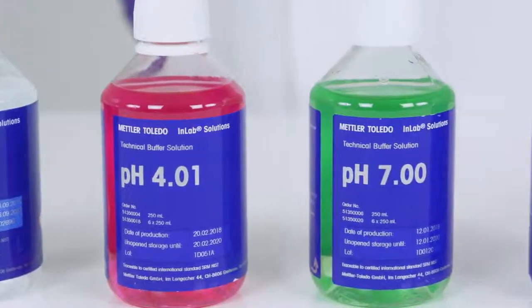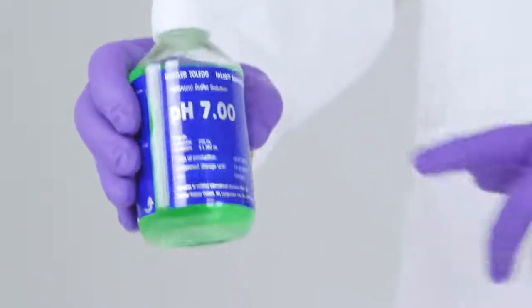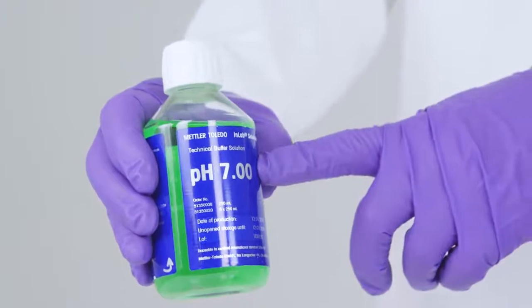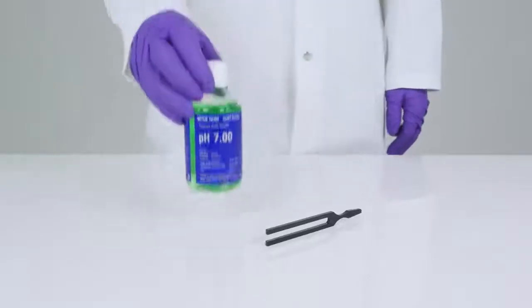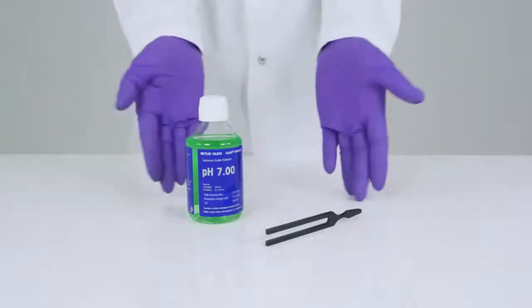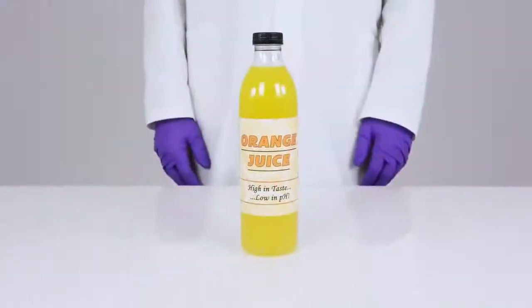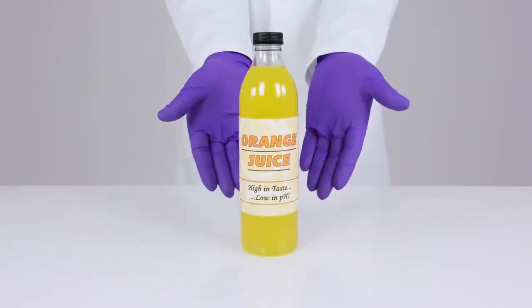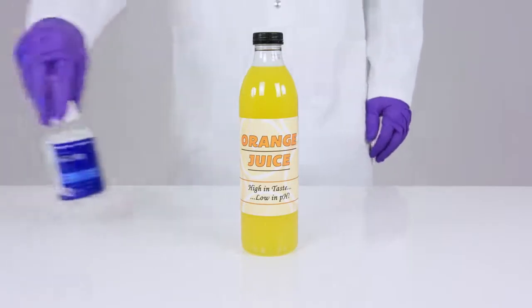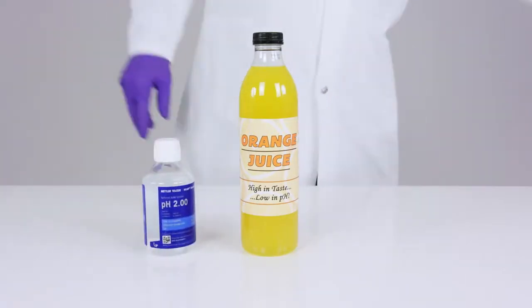Uh-oh, Hans. Sounds like more science. Buffers are liquids with known pH values, which act as reference points for the meter to compare its actual measurements, like with our violin and the reference pitch of the tuning fork. If you know roughly what the pH of your sample is going to be, then you may use two buffers for a two-point calibration. In this case, choose buffers with pH values that bracket the sample value.